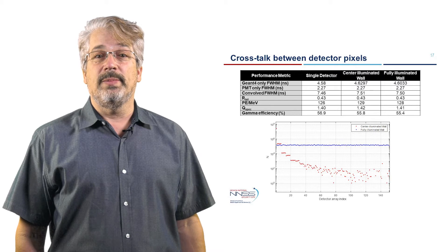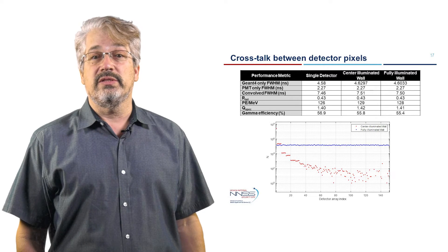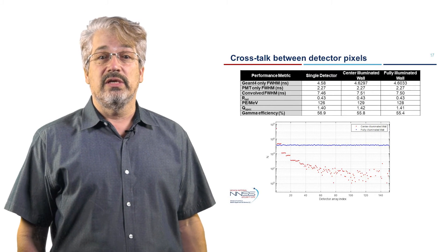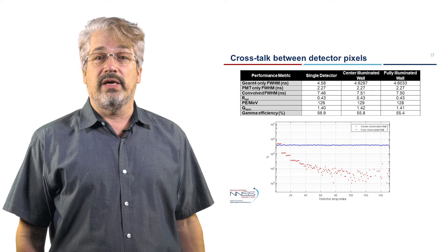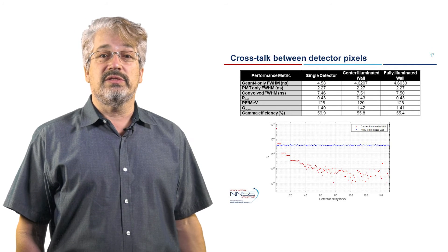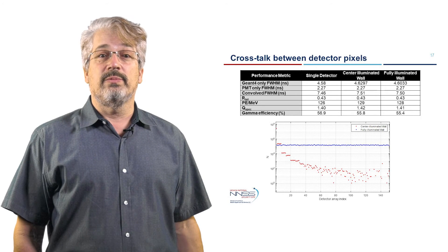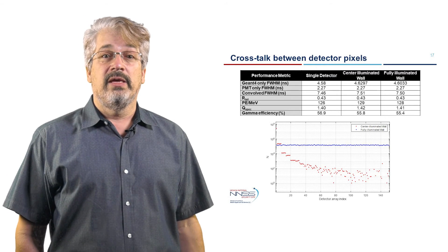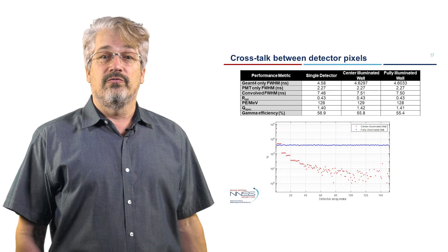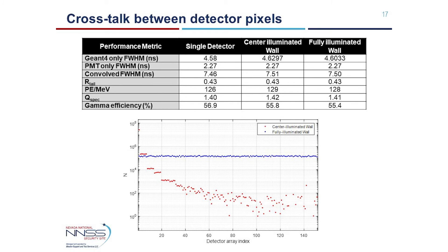In the fully illuminated case, the response of all 151 detectors is approximately the same. In the center-illuminated case, the center detector has the highest response, and as you move out from the center, the detector response decreases. This staircase distribution indicates the presence of crosstalk between neighboring detector pixels. Detectors at the same distance away from the center-illuminated detector have similar responses. Note that the detector array index starts with the innermost detector and winds counterclockwise outwards.